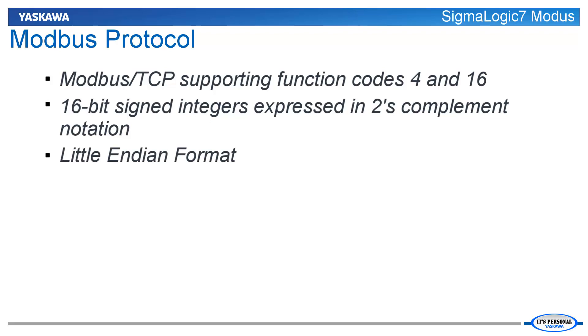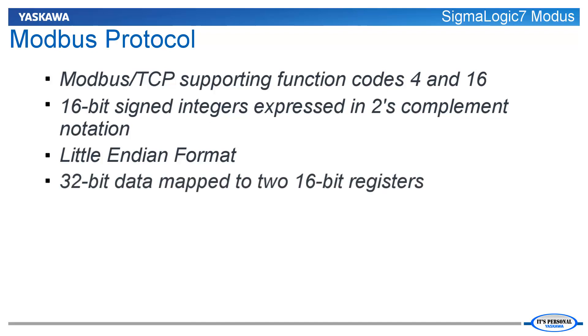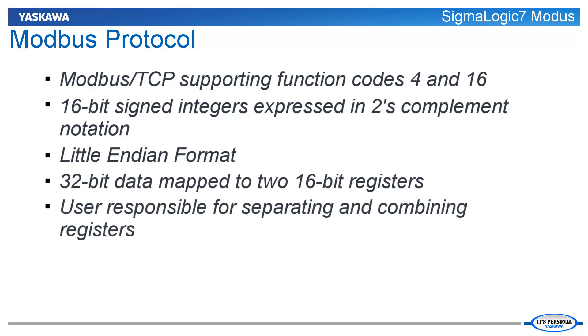Some data, such as position and speed feedback, is too large to be contained in a single 16-bit register and therefore is mapped into two consecutive registers. The user is responsible for separating and combining these registers as required. An important data transfer concept that must be addressed is the issue of data storage by CPUs.